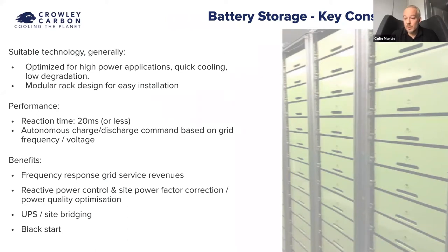On performance, you should really be looking to get up to maximum charge or discharge within 20 milliseconds or less, and that supports the enablement of those lucrative grid services we'll come onto later. It's not a phone call and a signal - these things need to be autonomous in terms of charge and discharge, based on grid signals and commands, to support the grid as and when it needs it, which is very lucrative. It happens in the background without plant users or clients even being aware, though they've consented to it, and it happens in milliseconds.